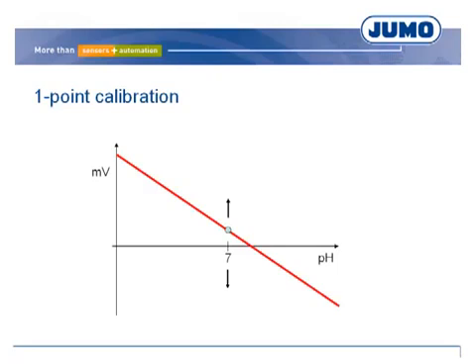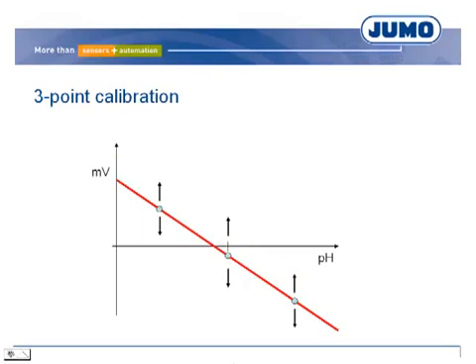Two further calibration methods are available. The one-point calibration is used, for example, in applications with ultra-pure water, using a measuring solution and a hand-held measuring device. The three-point calibration is used for measuring in both acid and alkaline media.